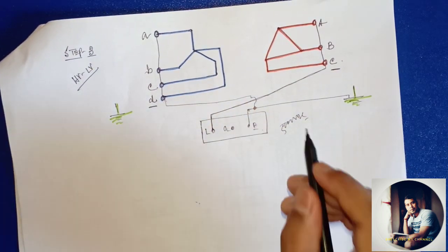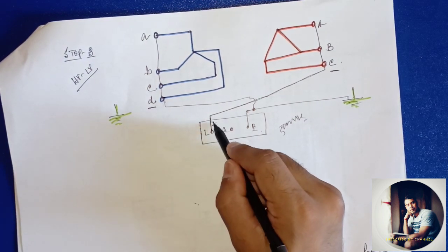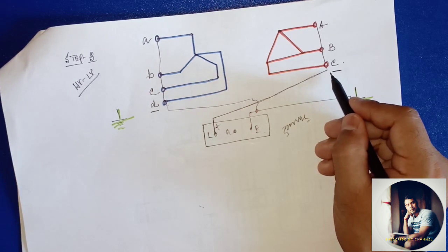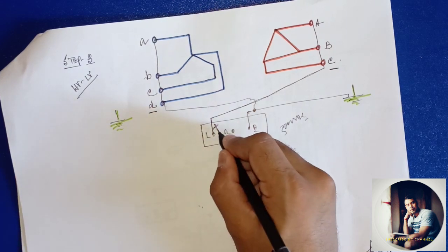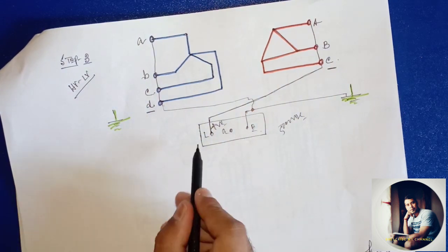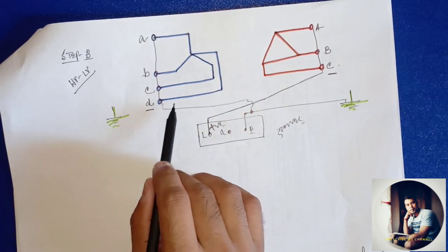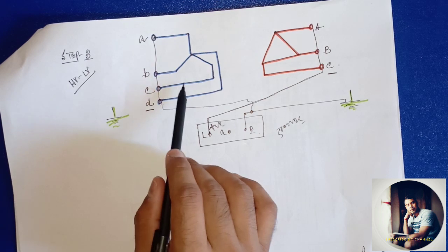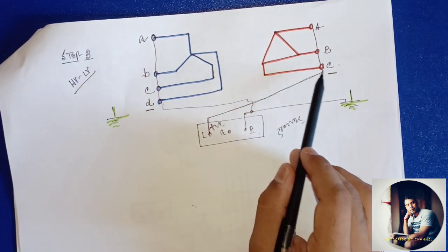In that case you have to be sure that your positive terminal gets connected with the high voltage side, that is the 11 kV side, and your secondary side is not connected with the positive terminal. In case you swap the terminals, the positive side can ruin the insulation of that star winding, because it is already a 433 volt system and the other is an 11 kV system.